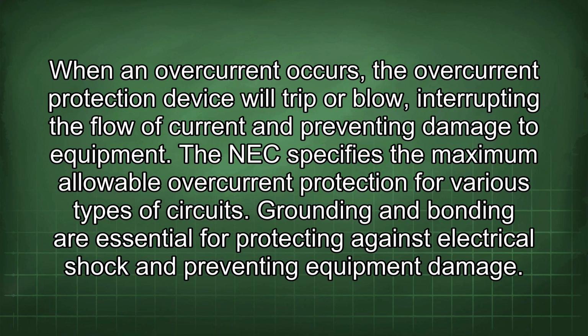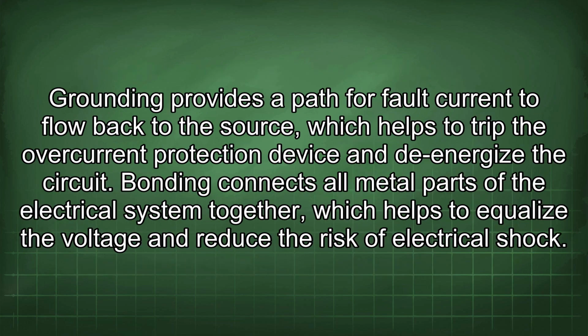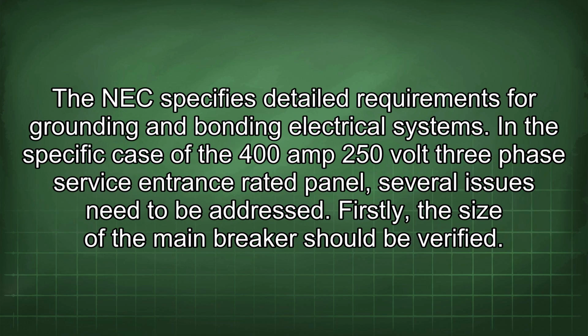Grounding and bonding are essential for protecting against electrical shock and preventing equipment damage. Grounding provides a path for fault current to flow back to the source, which helps to trip the overcurrent protection device and de-energize the circuit. Bonding connects all metal parts of the electrical system together, which helps to equalize the voltage and reduce the risk of electrical shock. The NEC specifies detailed requirements for grounding and bonding electrical systems.